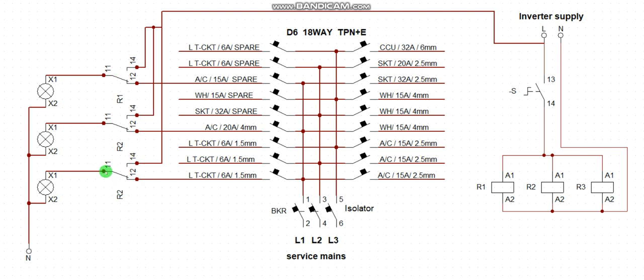Now the common of the contact is where the load will continue to go out. I use this load to illustrate the original load that is feeding. Now this is outgoing, outgoing, outgoing. Then you interface a relay to the outgoing. The common of these relays will remain to the outgoing loads. You see them light up here now. Then terminal 14 and terminal 12. 12 is normally closed. So maintain the outgoing circuit on normally closed, and take common to your load continuous.